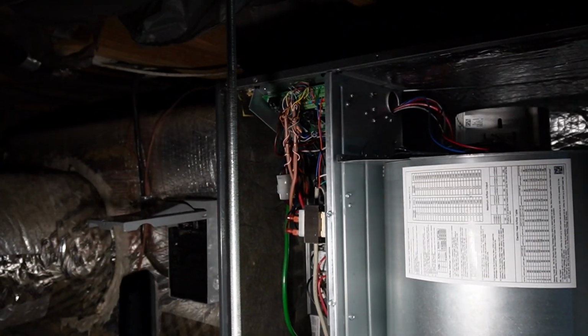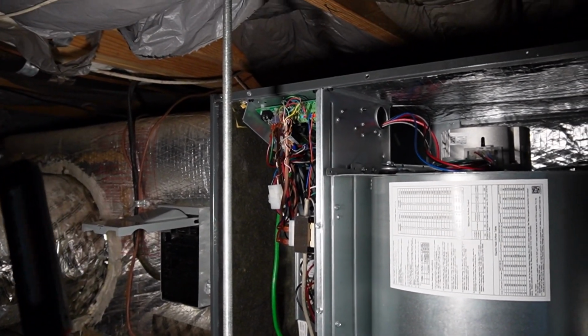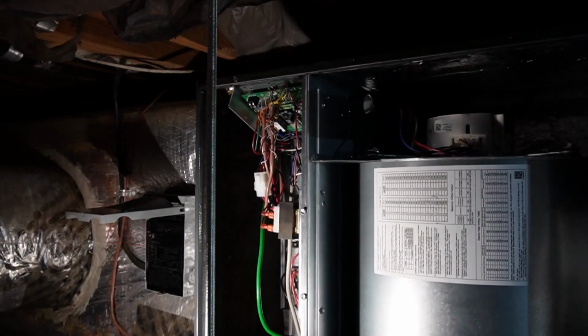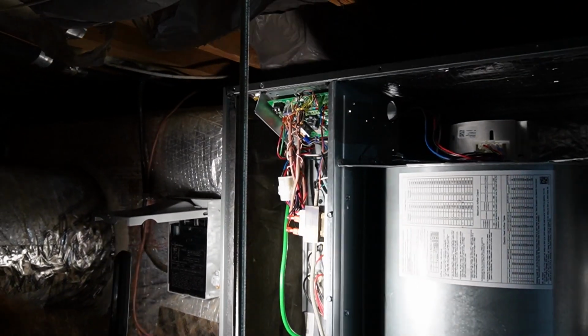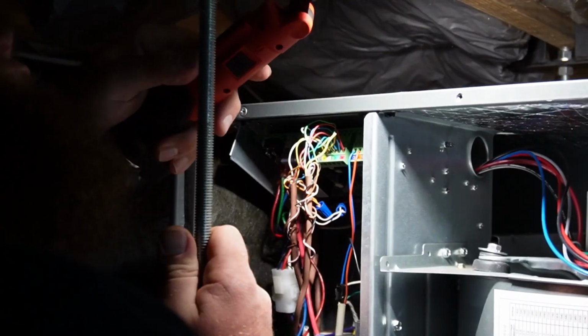So it's all adding up, that's where we're at. So the fact is, it was never set up for heat right, but it ran all winter without auxiliary heat. And now, since it was wired wrong, it's running the heat strips when it's trying to cool. And the electrical work is not up to specs.